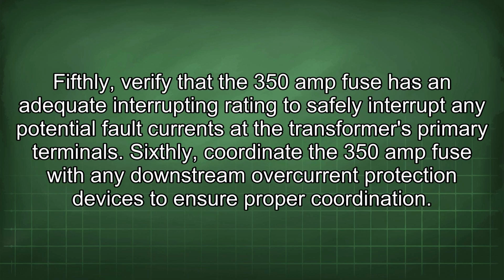Fifthly, verify that the 350 amp fuse has an adequate interrupting rating to safely interrupt any potential fault currents at the transformer's primary terminals. Sixthly, coordinate the 350 amp fuse with any downstream overcurrent protection devices to ensure proper coordination.